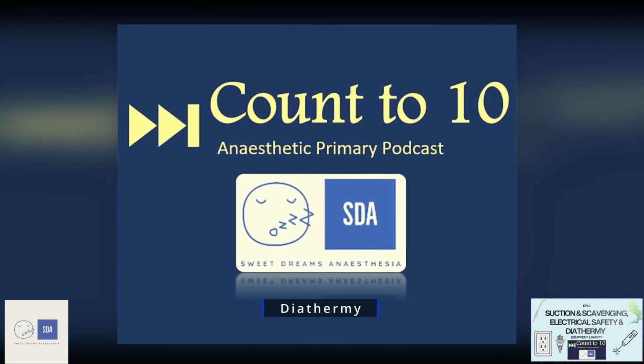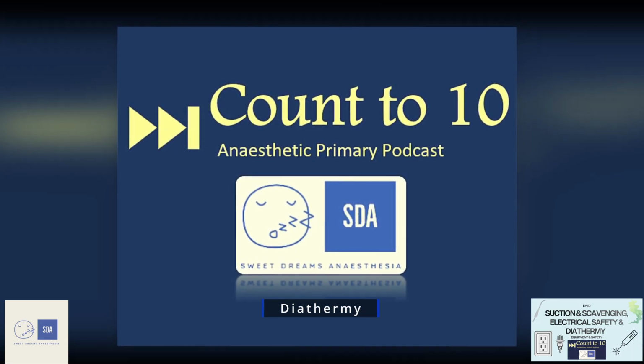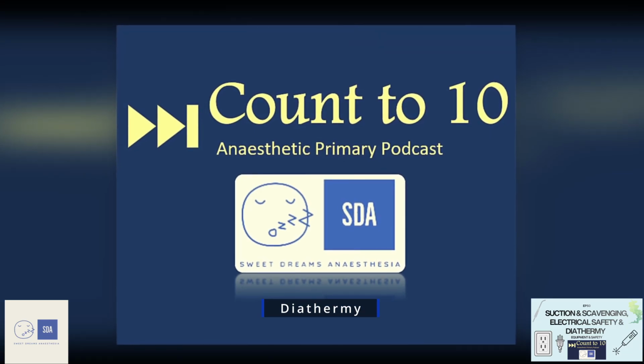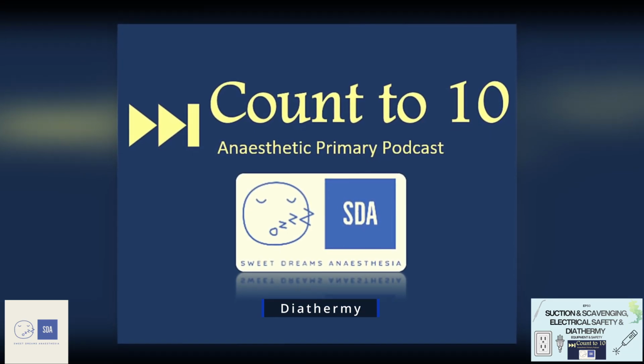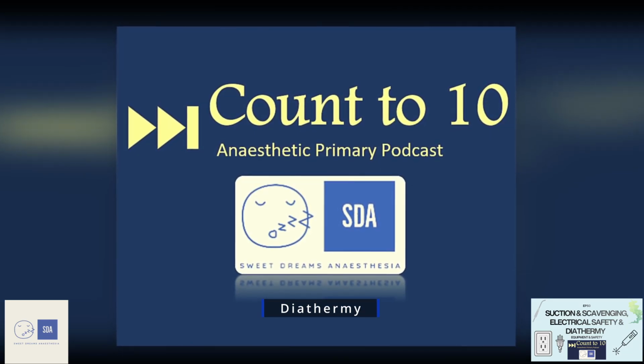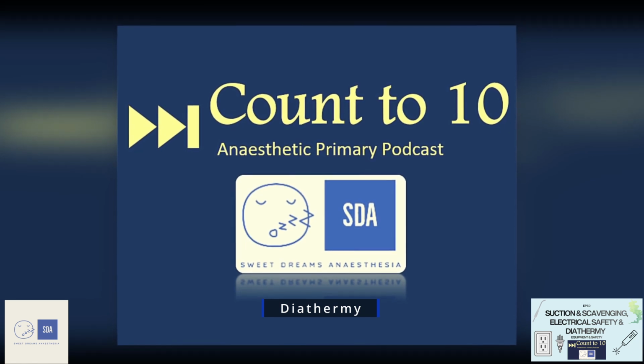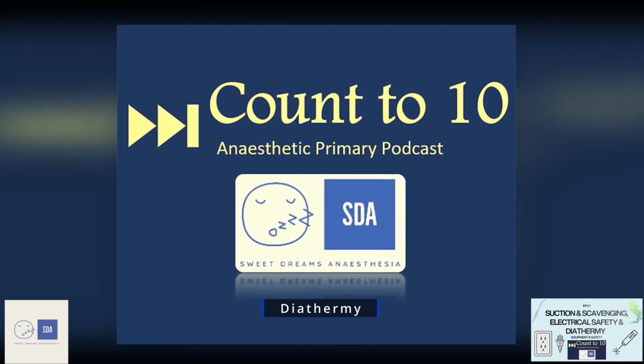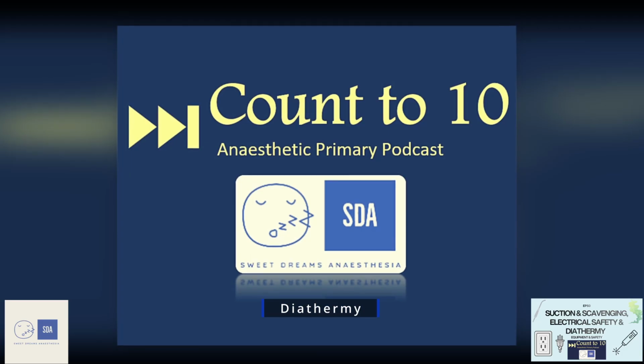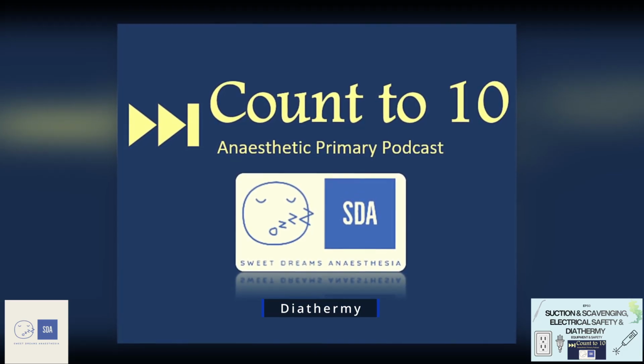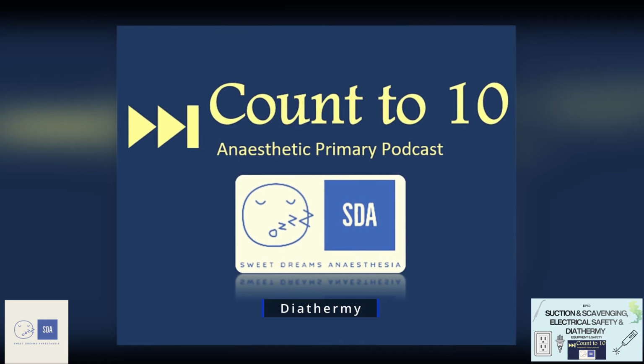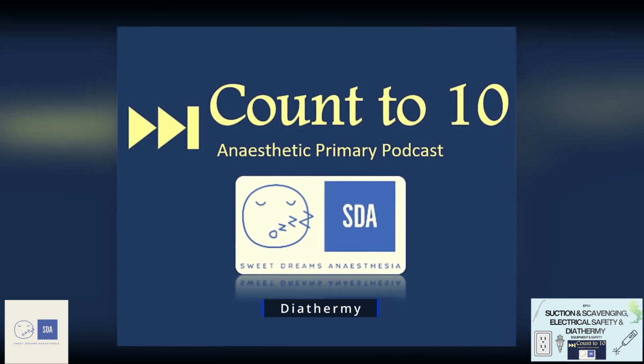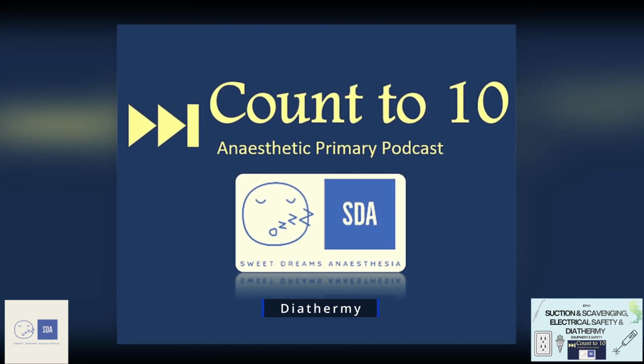In terms of the functions of diathermy, we've already mentioned that it can cut and coagulate, and the way it differentiates which one of these aspects it does is all based on the current waveform. So for it to cut, it uses a low voltage, typically 250, to produce a high current at a continuous sine wave. This continuous sine wave allows for rapid heating and boiling of that intracellular fluid.